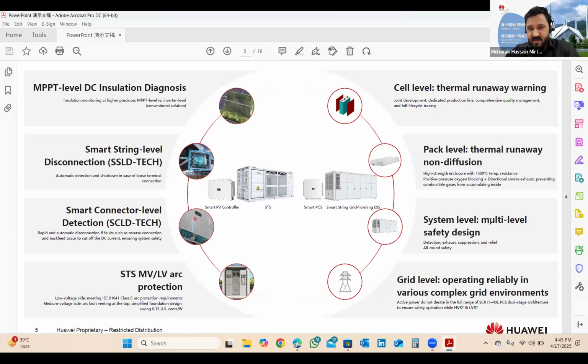There is the thermal runaway concept. There are huge containers of 2 megawatt, 4 megawatt available, and in the 2 megawatt container there is a huge energy density in terms of small racks. So safety of every rack, every compartment is very important. There's pack level safety, rack level safety, and then system or container level safety.